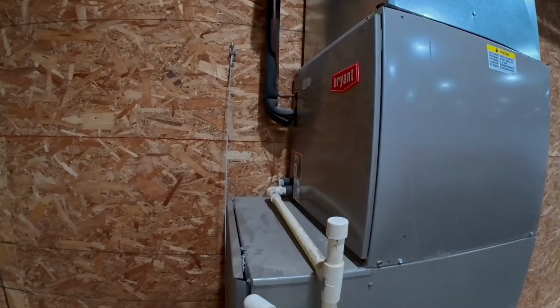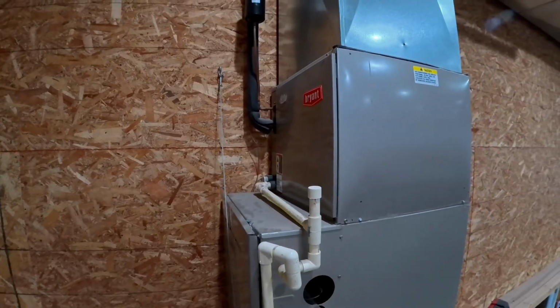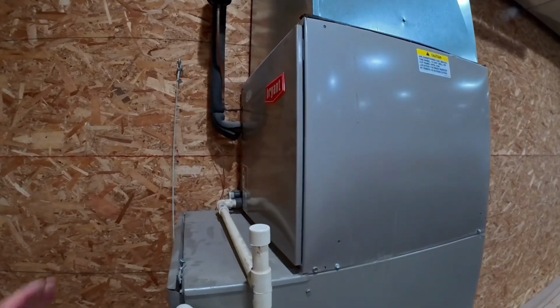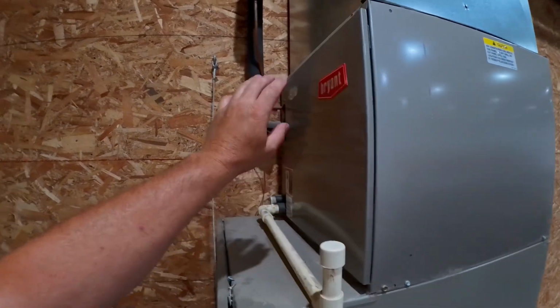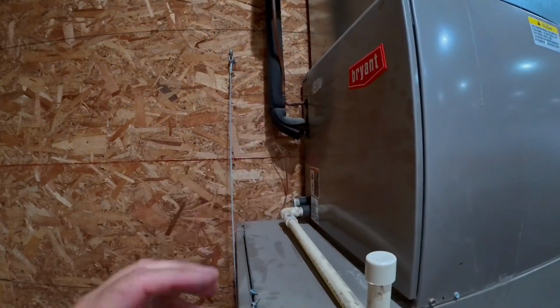The second sign that an AC is going to show you is an ice buildup anywhere on the unit, anywhere on the plenum, anywhere on the line sets, or anywhere on the outdoor unit. Ice buildup anywhere on the system can be attributed to two situations. The first situation, and the most common, is poor airflow across the indoor coil. Mainly, your filter's plugged.